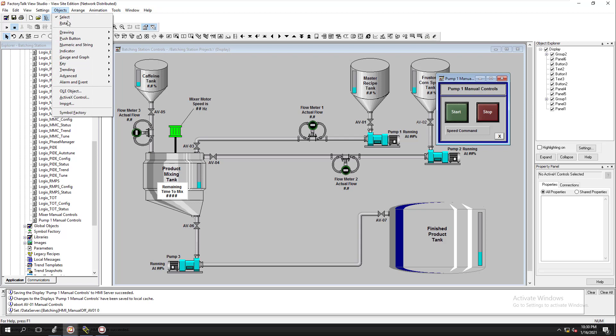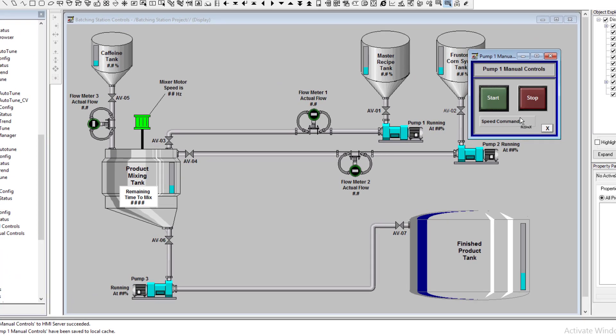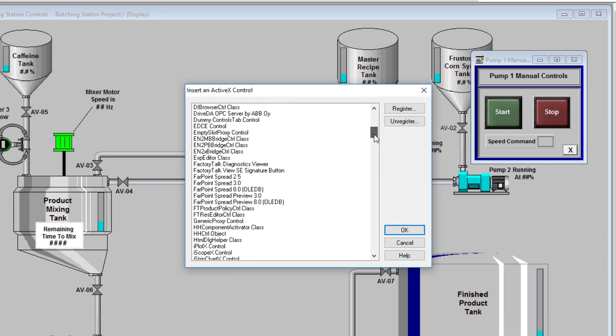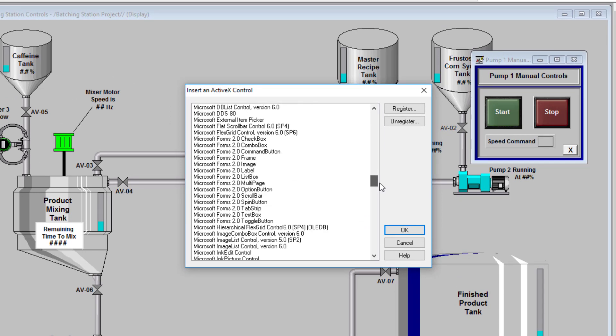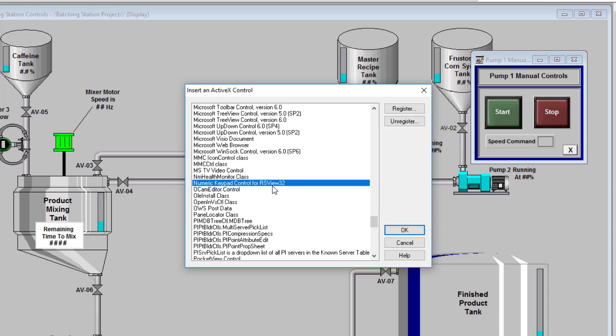Go to the top, go to Objects, then go to ActiveX. I'm going to draw it out right here, and then I'll select and insert the ActiveX I'm going to use. We're going to do a numeric display, so scroll down to Numeric Display — that's the Numeric Display Control for RSView32. That's the most compact, easiest to use, and most frequently used one.